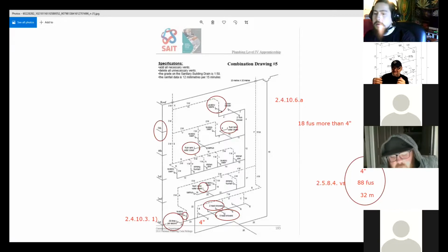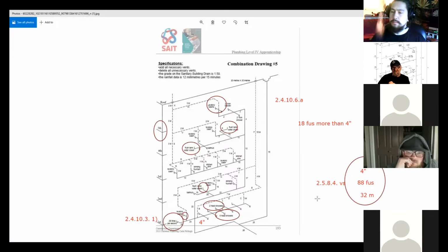Now I'm going to give you the easy way. On any building that's 5 stories, and obviously it's going to have a certain load of fixture units, 95% of the time it'll be a 3 inch vent stack. So even if you forget what I just showed you, on a drawing, if it's a 5-story building, there's a 95% chance it's going to have a 3 inch vent stack. Most vent stacks out in the field are 3 inches because of load and developed length.